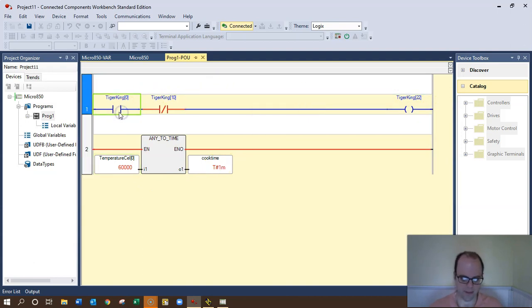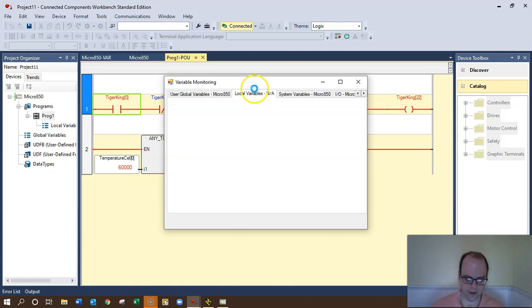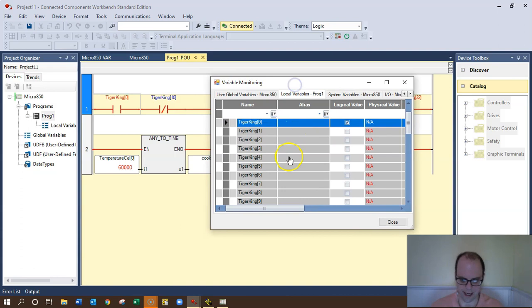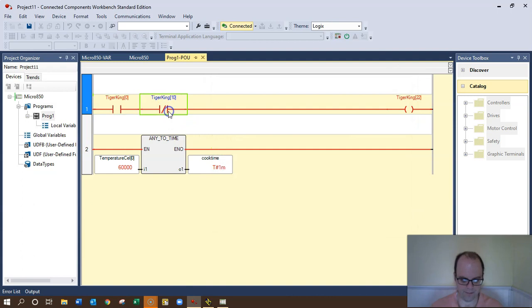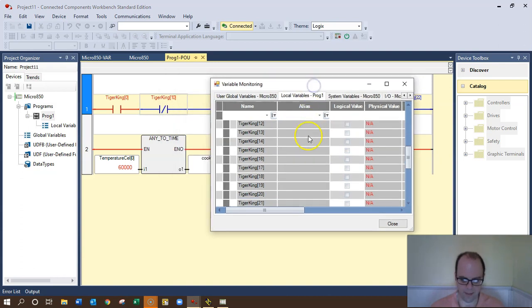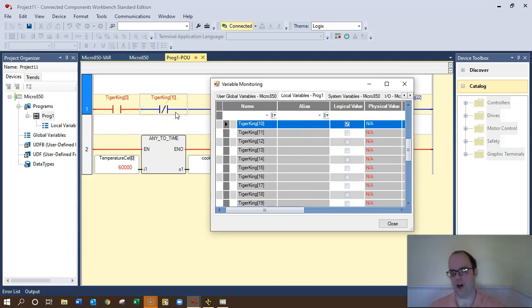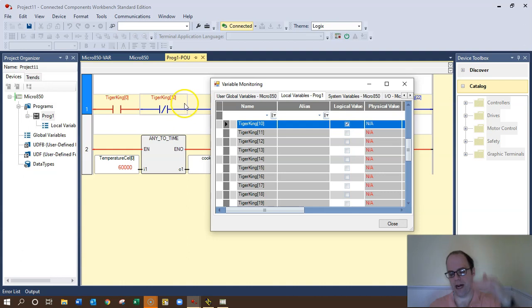So with this logic command, if I wanted to, if I hit control T, it's going to toggle the bit for me. And look, it completes the logic. And if I double click on it, I can monitor. And look, it's on. If I go down to Tiger King 10, it's off. But once I go here, once I close this and toggle the bit, the rung goes false. And then you can see under that memory bit, it's on. Because remember, when it's an XIO, it's asking the question, is it false? And if it's true, then this loses its power.